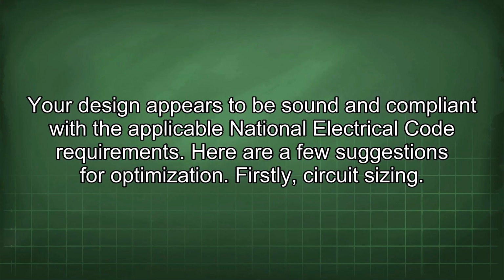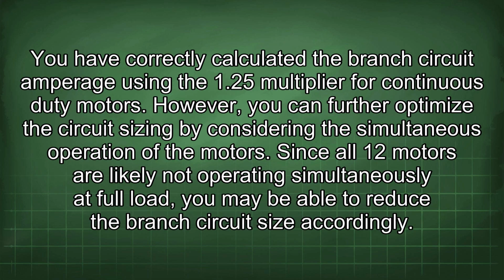Your design appears to be sound and compliant with the applicable National Electrical Code requirements. Here are a few suggestions for optimization. Firstly, circuit sizing. You have correctly calculated the branch circuit amperage using the 1.25 multiplier for continuous duty motors.